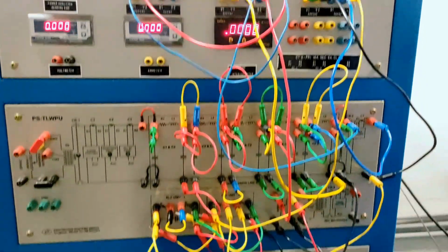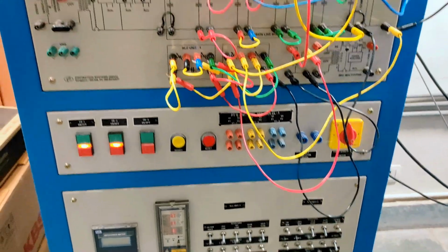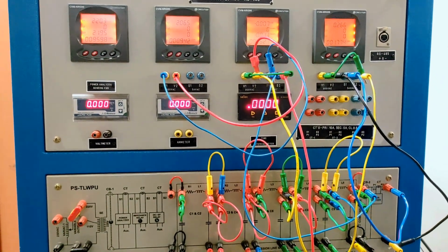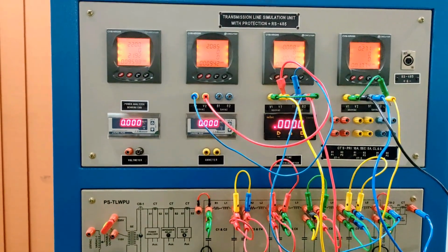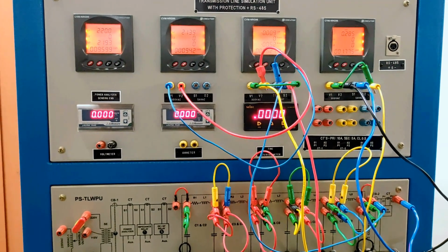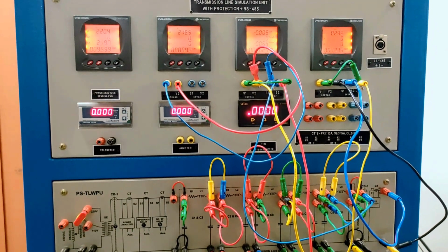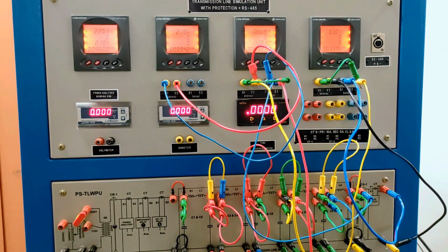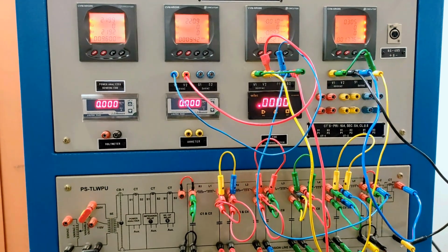So now if I increase the load once more, above 200, let me turn on 300. So you can see I have turned on 300 and here the voltage is 206. So I have to increase it. So what do I have to do? I no need to turn on the capacitor once again. Only I have to adjust the output voltage of the auto transformer. So by adjusting the output voltage of the auto transformer, I am getting 0 voltage regulation. So that is 220.